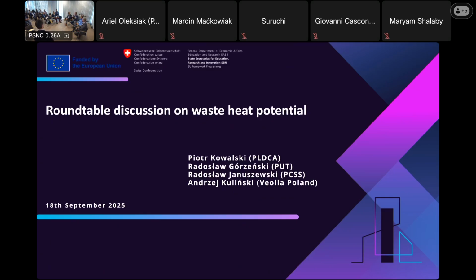In case of heat pumps, we talk about COP, coefficient of performance. The smaller the temperature difference between the low source and the supply source, the lower this difference, the higher the COP. So if we talk about whether it's reasonable, we have to consider what options we have. We only have air and ground, and each time the temperature difference is much higher, so the results are worse for air and ground source.